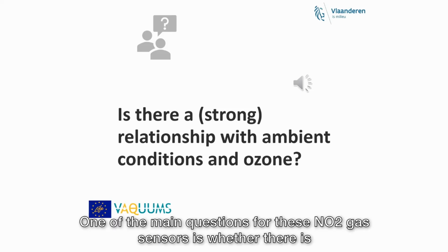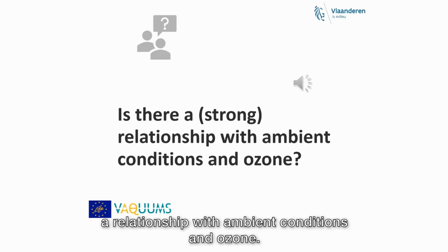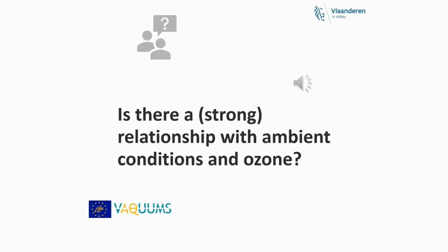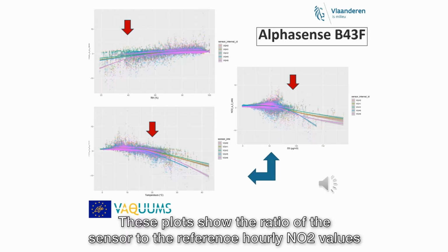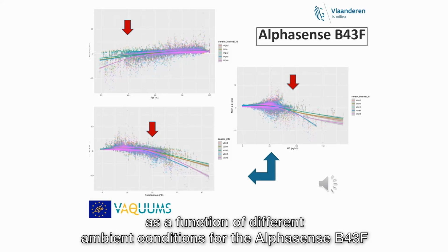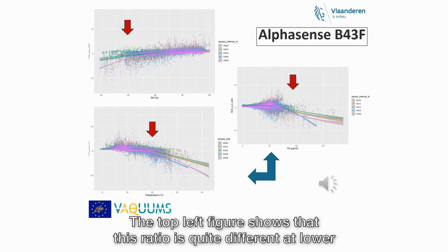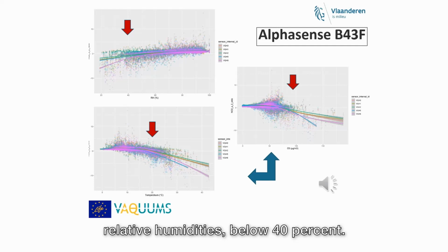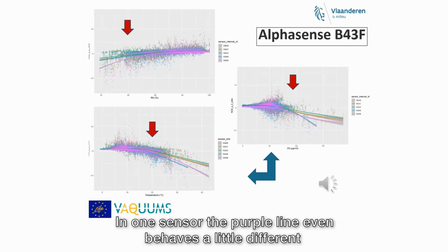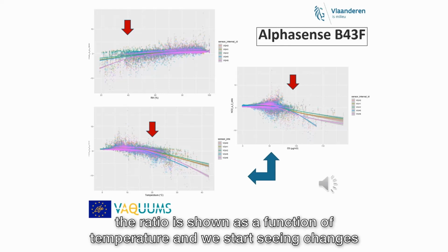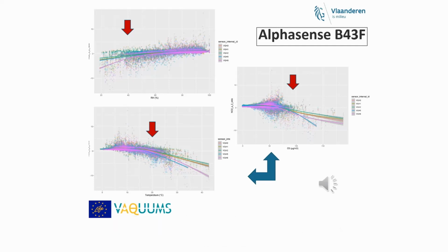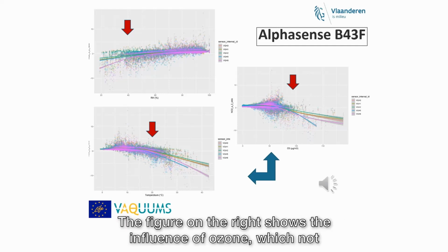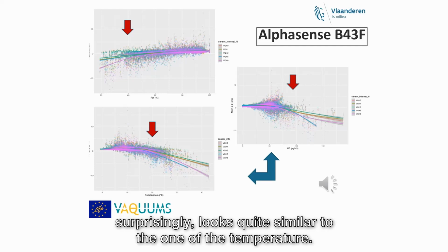One of the main questions for these NO2 gas sensors is whether there is a relationship with ambient conditions and ozone. These plots show the ratio of the sensor to the reference hourly NO2 values as a function of different ambient conditions for the AlphaSense B43F. The top left figure shows that this ratio is quite different at lower relative humidities, below 40%. And one sensor, the purple line, even behaves a little different from the other 4. In the bottom left figure, the ratio is shown as a function of temperature, and we start seeing changes for temperatures above 20 degrees Celsius. The blue and purple sensors behave different from the other ones. The figure on the right shows the influence of ozone, which, not surprisingly, looks quite similar to the one of the temperature.